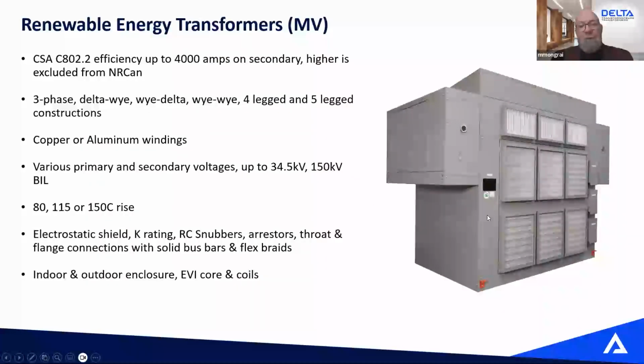We also do some large medium voltage transformers directly connected to a large solar panel farm, massive inverter, and we can connect those transformers already back to the utility all the way up to 35 kV, 150 kV BIL. So same principle as a small low voltage transformer, but for those massive ones. We did a few large projects like that over the last few years. So again, it's all custom built depending on your requirements.